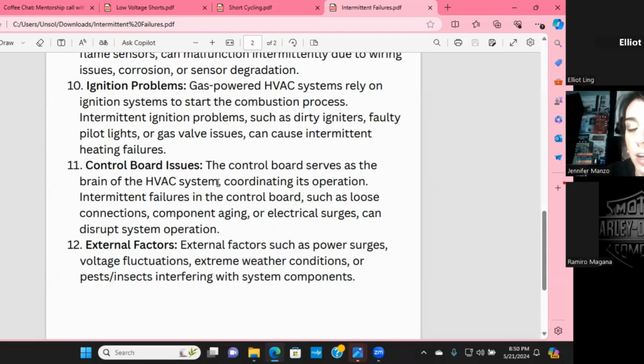So just because your system is intermittently lighting and let's say it doesn't have proper airflow, that doesn't mean you have a bad board. A lot of people think that if it's a couple of things, well, that automatically means bad board. It doesn't. You need to test every single component and make sure it's the board. But what a lot of people think is that one weird thing, say it's skipping airflow and going back to gas or ignition, is the board. It's doing that because it's not getting its correct airflow, not because the board is messed up and telling it to do funky things. So we always need to verify. But control board issues, my rule of thumb and the only rule of thumb that I will ever have for control boards, if it's one thing, it is definitely not your board. If it's multiple things, then it could be your board. And that is the best I will give when it comes to boards.